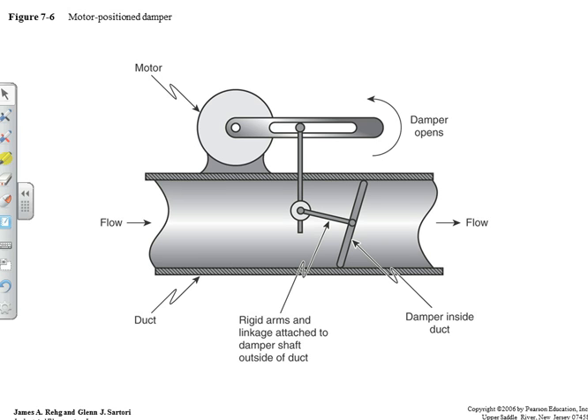So we put in a damper just above the parts room, to the outside. We open that damper before we turn on the fan, bringing in outside air to replenish what the ventilation fan sends out. Now we don't get a vacuum on the building when we turn it on.